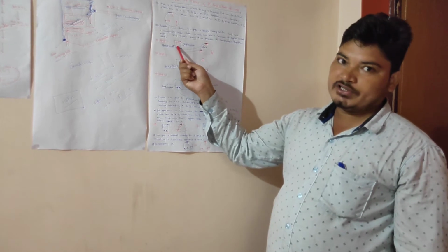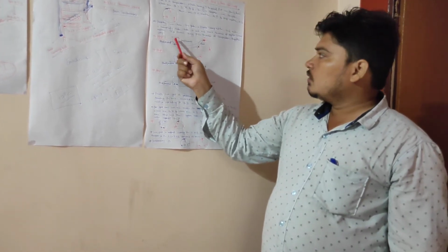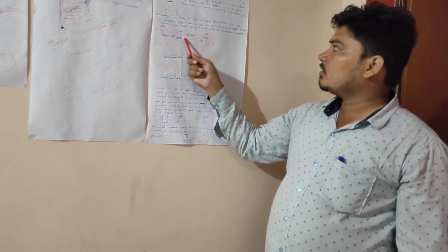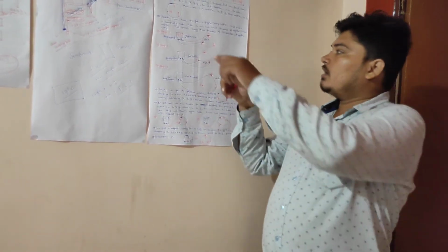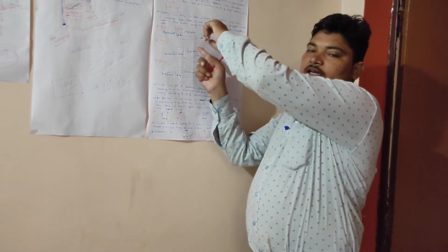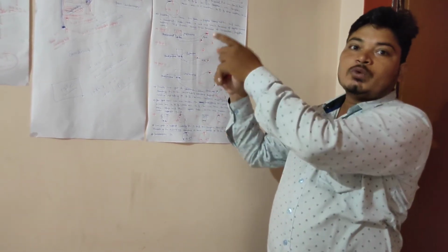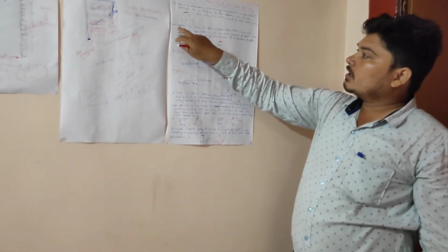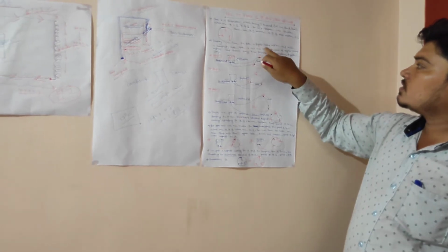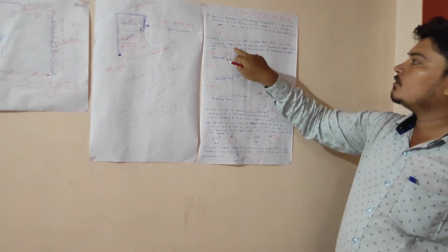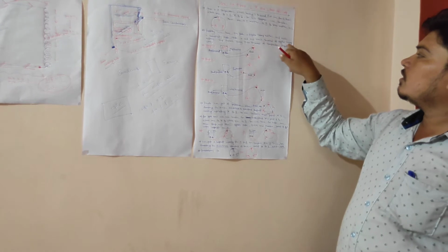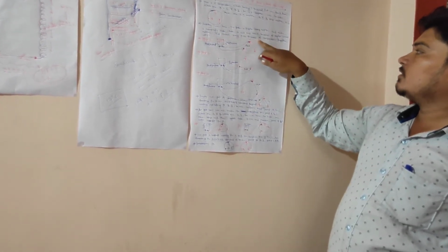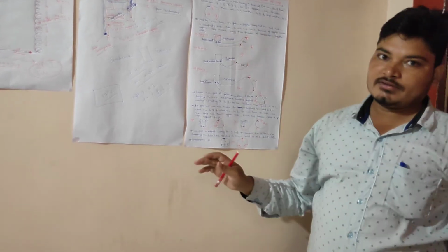Make it continuity mode, take the black and red terminals, and touch every two electrical terminals of the compressor together. Here I have written: firstly take a digital clamp meter, set continuity mode, take the red and black terminals and touch every two electrical terminals of the compressor.